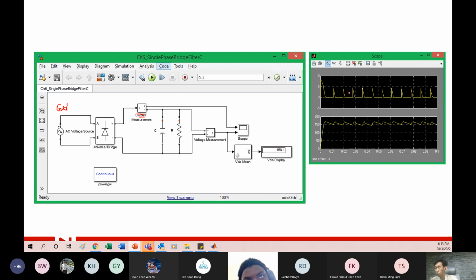Low power is no issue at all, especially at LV. LV 400 volt and below, you can connect 10 computers and there's no issue. But when dealing with MV, that is an issue because MV directly affects the grid. TNB mandates that the THD cannot be more than 5%. If it's more than 5%, they will never approve it during commissioning. If you tell them your harmonic is 6%, can it pass? They will refuse — you cannot even commission it. You have to solve it first.